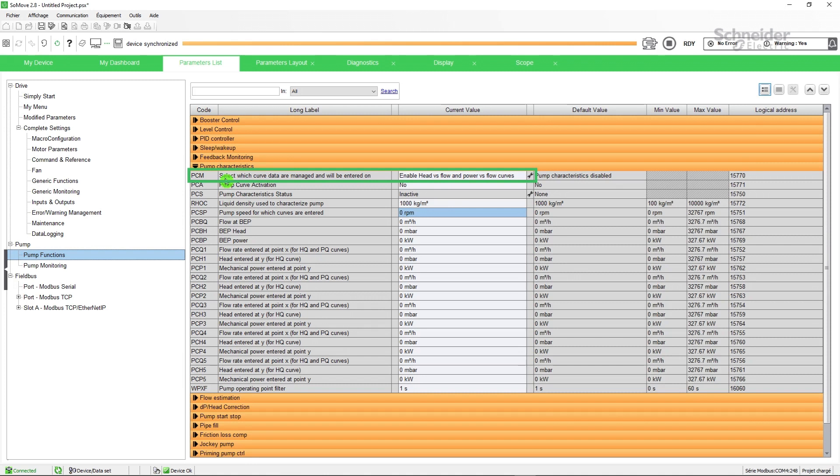The mode parameter used to select the curve data is set to enable head versus flow and power versus flow curves. Enter the values of the pump speed for which curves are entered. Enter the values of the flow rate, the head, and the power for the BEP and the five points you have selected on the curves.